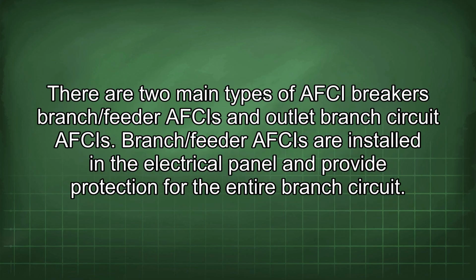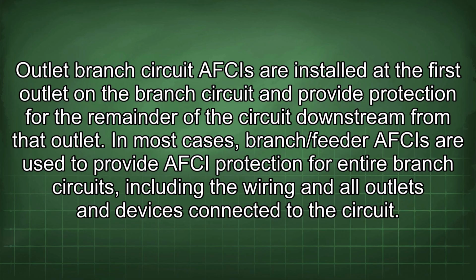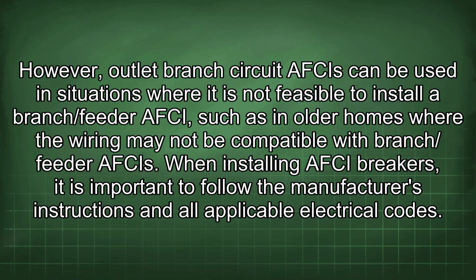There are two main types of AFCI breakers: branch/feeder AFCIs and outlet branch circuit AFCIs. Branch/feeder AFCIs are installed in the electrical panel and provide protection for the entire branch circuit. Outlet branch circuit AFCIs are installed at the first outlet on the branch circuit and provide protection for the remainder of the circuit downstream from that outlet. In most cases, branch/feeder AFCIs are used to provide AFCI protection for entire branch circuits, including the wiring and all outlets and devices connected to the circuit. However, outlet branch circuit AFCIs can be used in situations where it is not feasible to install a branch/feeder AFCI, such as in older homes where the wiring may not be compatible with branch/feeder AFCIs.